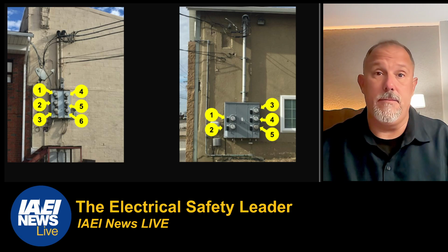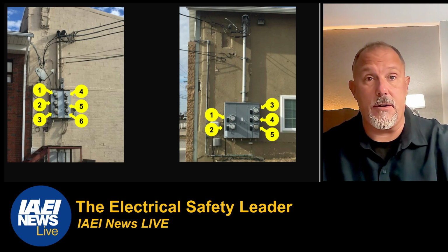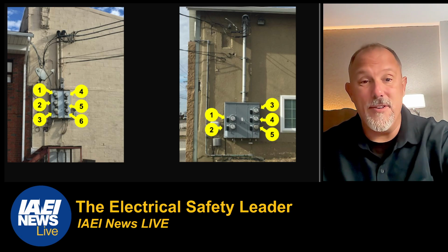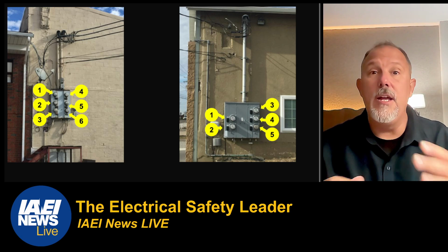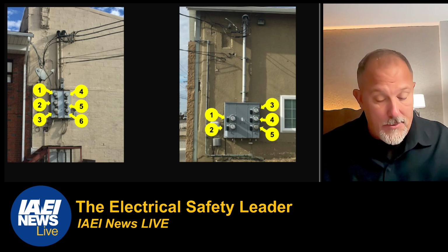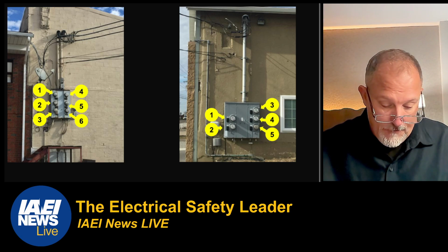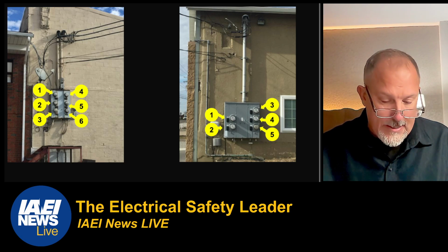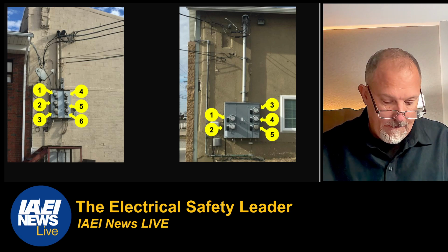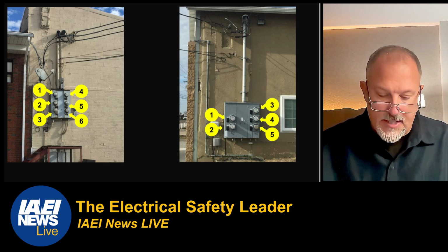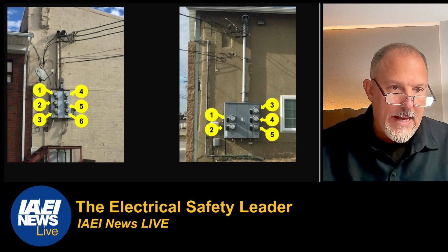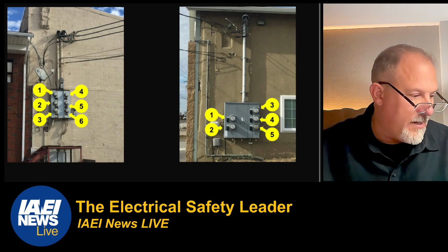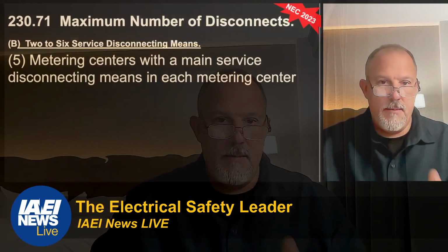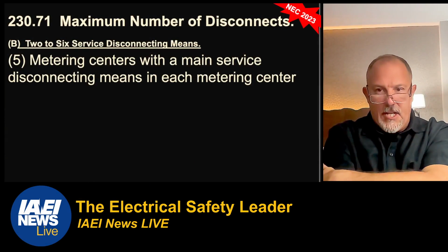Well, meter centers have the same problem. Now, the standards are trying to figure out how to address a meter center to where you can open an enclosure for a circuit breaker and not have anything else exposed, barrier off the line side, and still have 6 disconnects. But I'm telling you, it's going to be a tough one. So what we did was we made a change where we recognized that in 230, we added a line item in 230.71. We added a specific line item: metering centers with a main service disconnecting means in each metering center.